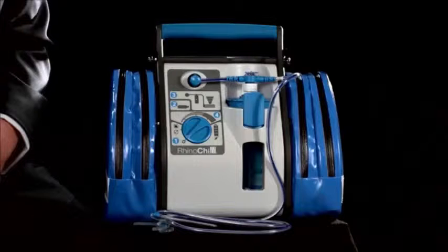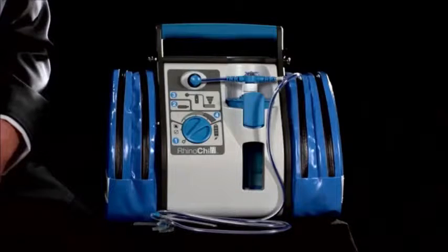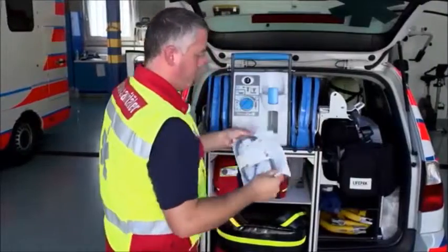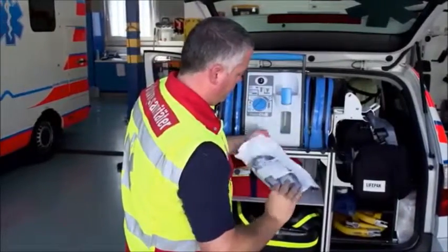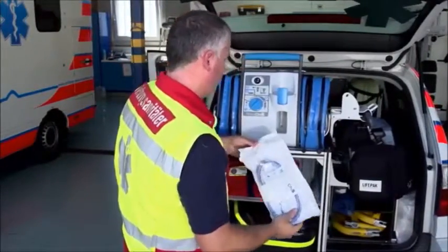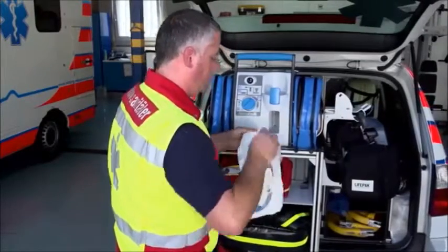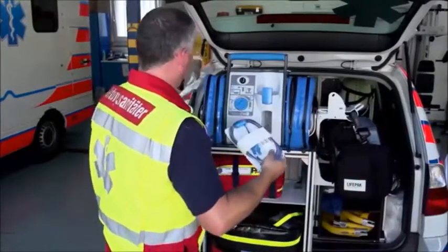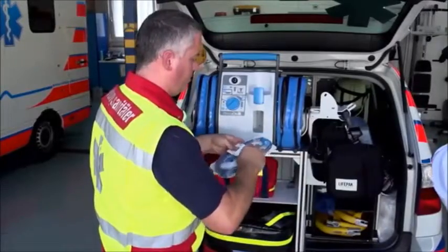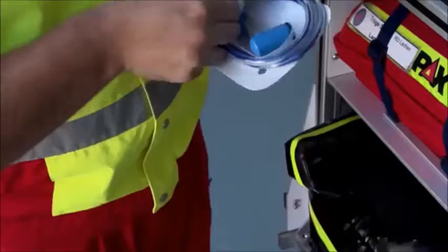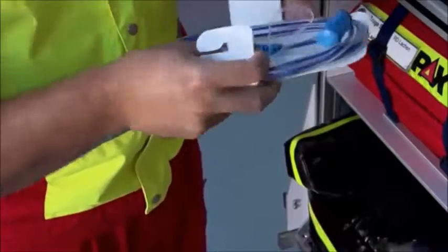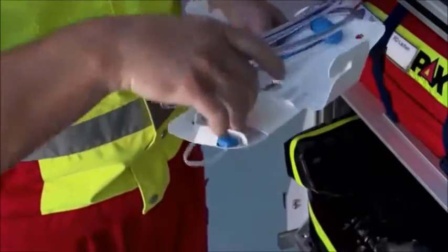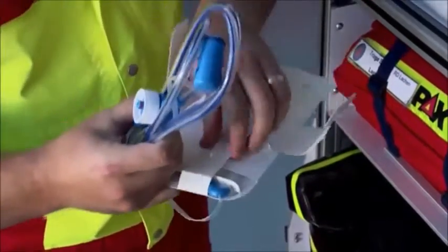The Rhinochill system consists of three separate components: the transnasal evaporative cooling catheter, the coolant, and the control unit. Let's look at these a little closer. The transnasal evaporative cooling catheter is a sterile, single-use device that delivers the cooling vapor into the nasopharynx to begin the induction of hypothermia. The catheter assembly is one continuous part that contains the connector to link it to the control unit, the coolant bottle interface and cap, the filter, the liquid flow indicator, and the delivery tubing.